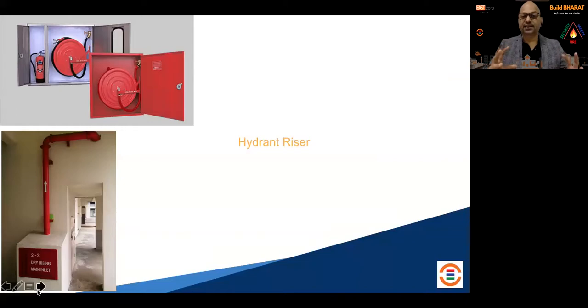the riser with the direction of flow. Your cabinet size for various dry riser or wet riser or pump service inlet, how they are going to be mounted, where it is going to be mounted, whether they are in a box or open. If it is a box, whether it is with a key or without a key, with glass or without glass. So these are all installation requirements.